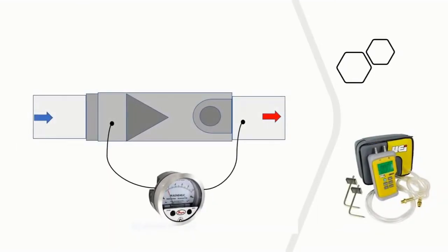The system must operate within the manufacturer's maximum pressure for the ductwork. This is called external static pressure. All manufacturers have a maximum rating. Exceeding this will cause excessive noise, increased operation costs, and affect the reliability and lifespan of the equipment. Sadly, many contractors don't even check.